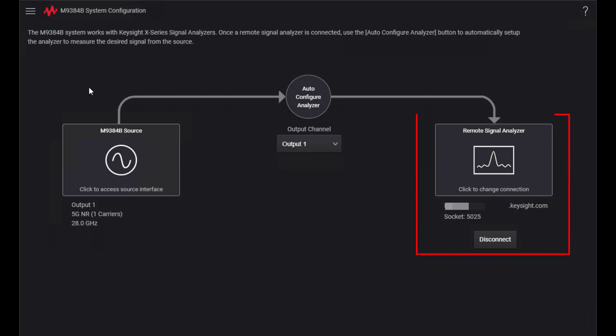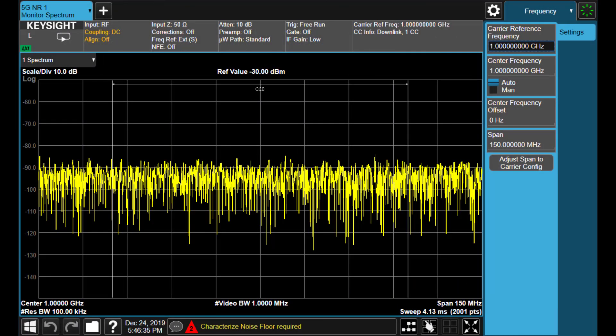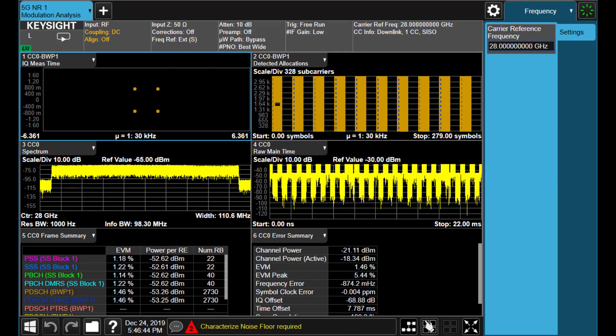Here, you can configure the X-Series Signal Analyzer you want to pair with VXG. Then, pressing the Auto Configure Analyzer button pushes the settings to the linked analyzer automatically. As you can see, the X-Series Analyzer is configured and starts making measurements.